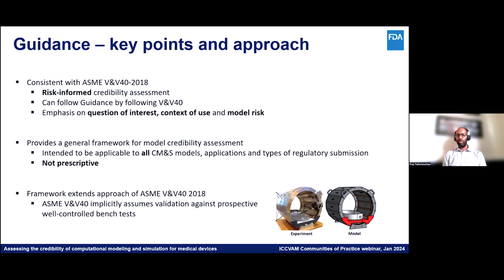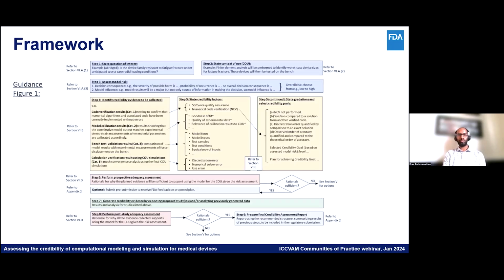But if you develop such a model, how can you validate it? It's very difficult to validate that using clinical data. It's often validated using experimental data. So that's an example of bench testing. But we needed a framework that's very general, for all sorts of applications and models and all sorts of different ways of validating it. That's why we developed this guidance, which generalizes V&V 40.